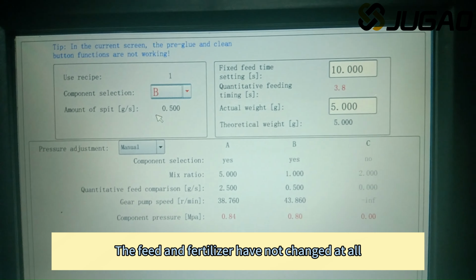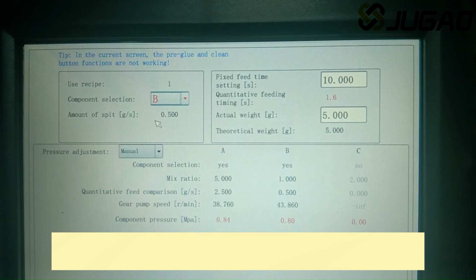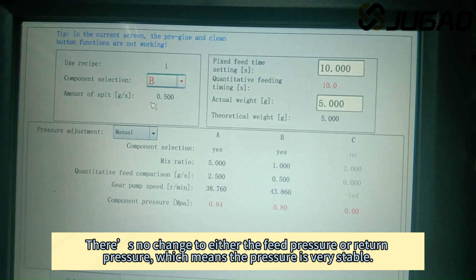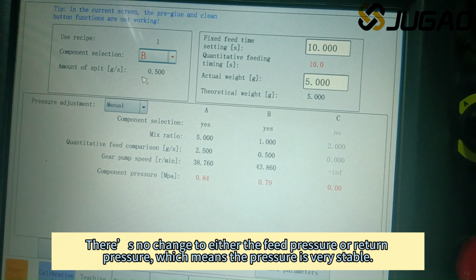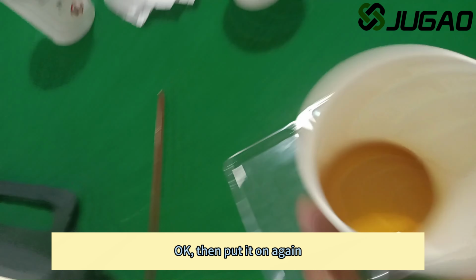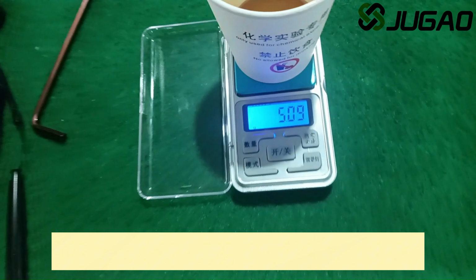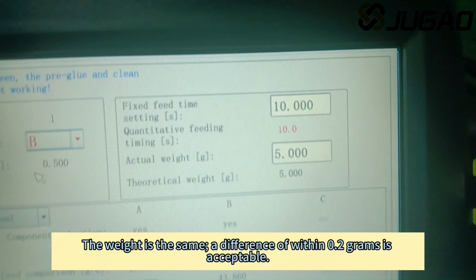The feed pressure and return pressure have not changed at all, which means the pressure is very stable. Okay, then put it on again. The weight is the same. A difference of within 0.2 grams is acceptable.